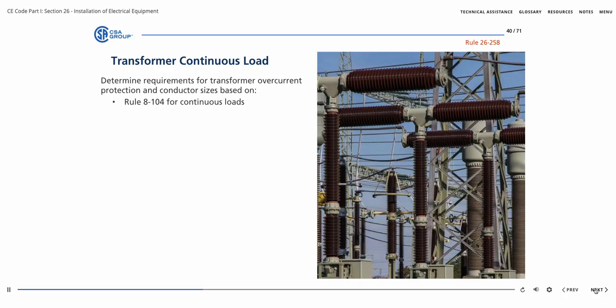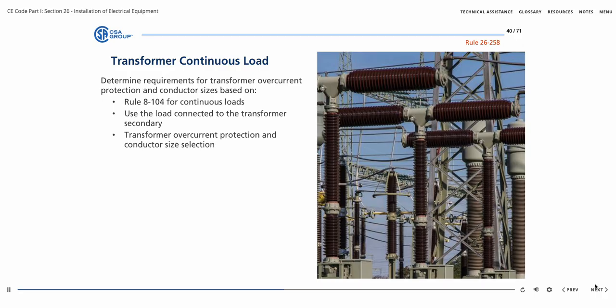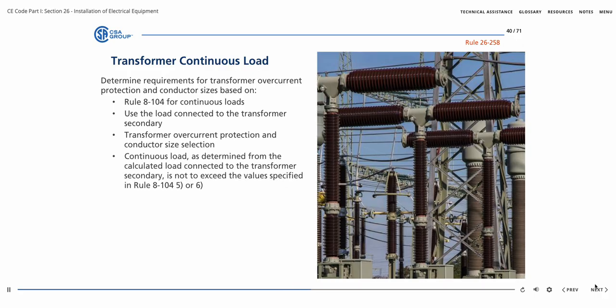It is not the rating of the transformer that is used, but rather the load connected to the transformer secondary. For the purpose of transformer overcurrent protection and conductor size selection, in accordance with Rules 26-250 through 256, the continuous load, as determined from the calculated load connected to the transformer secondary, is not to exceed the values specified in Rule 8-104, Item 5 or Item 6.